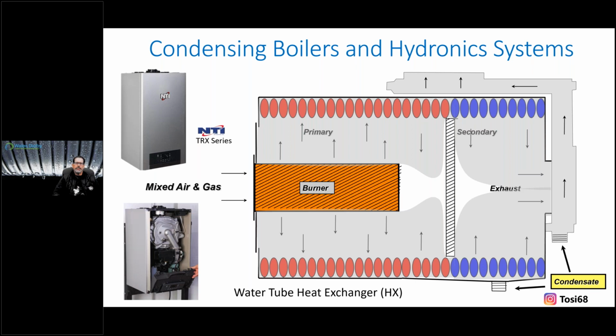There is something to be said about the other side of taking advantage of this, which is giving it an outdoor reset, right? Make sure you're installing the sensors. The outdoor sensors give a lot of input on what the design conditions are outside. Without it, we're basically just going off a high limit. It will modulate based off of flow or temperature through that heat exchanger, but we're not seeing the full capabilities of that modulation. So it's really best to see that, all right? And we'll talk about that in a little bit.